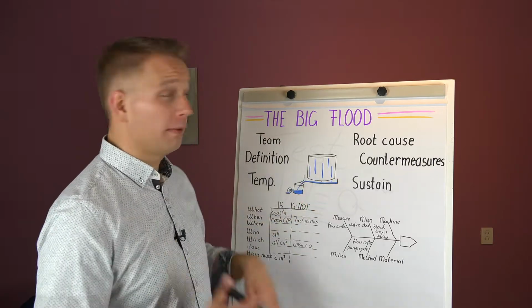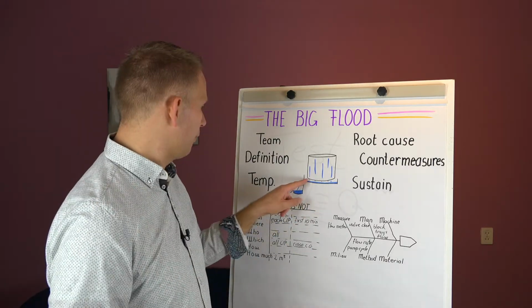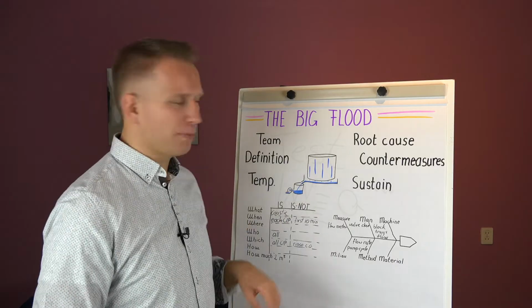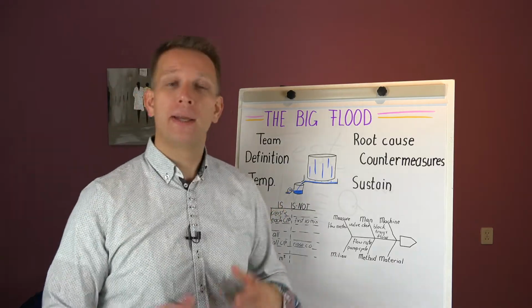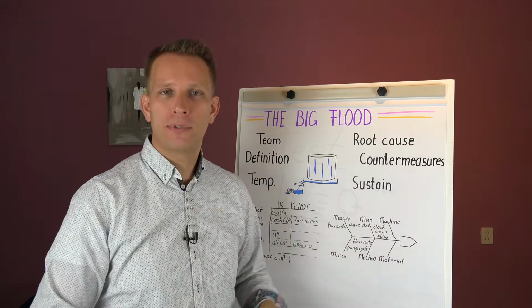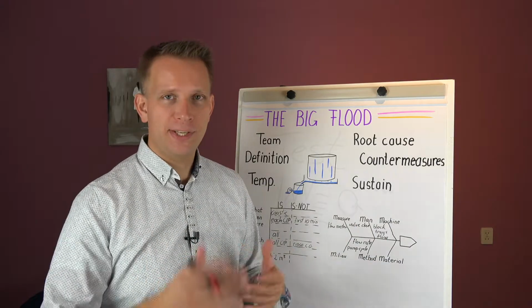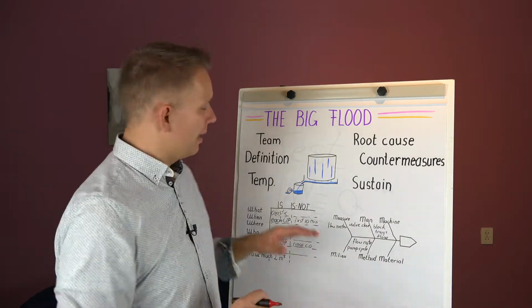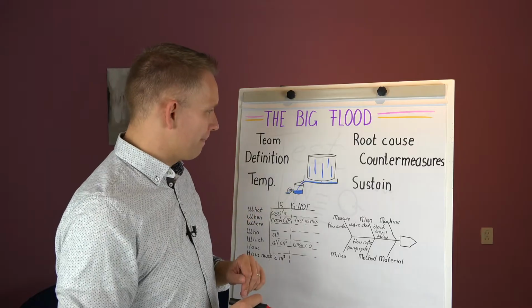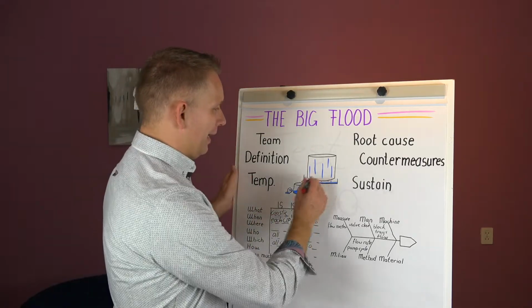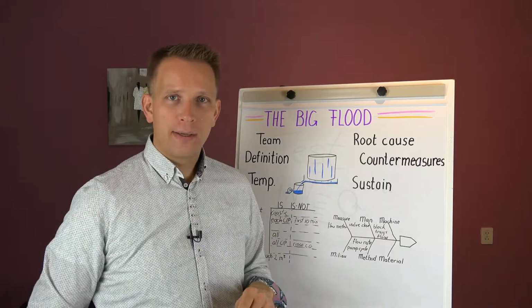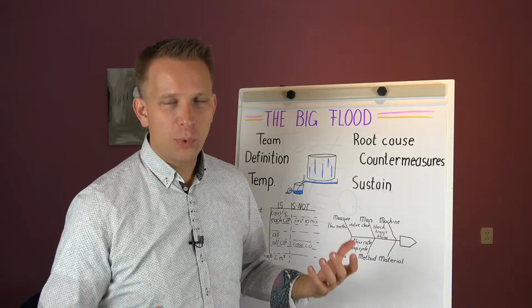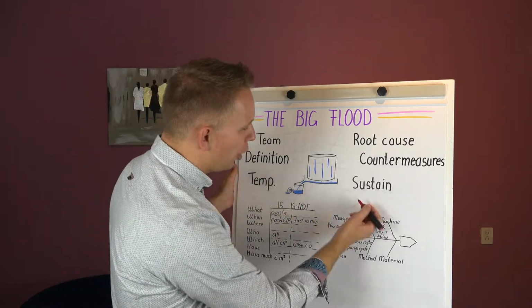Then the water or cleaning water flows to sort of an extra small tank where it is pumped away back into our CIP system or in certain phases down the drain. Now what was happening is that it was not pumping away quick enough, or at least what we saw happening was that water would overflow.